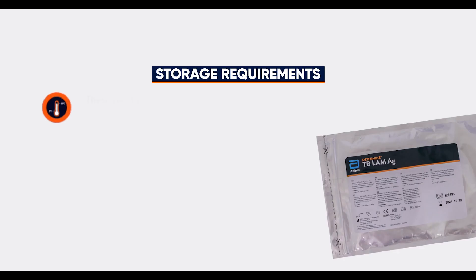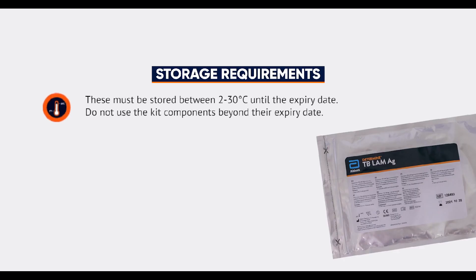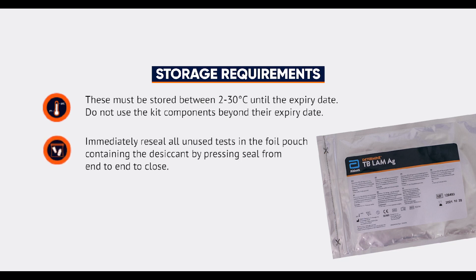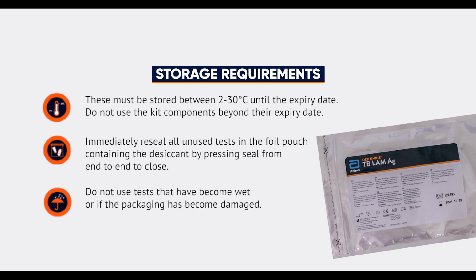The Determine TB-LAM antigen test cards have specific storage requirements to maintain quality and reliability. These must be stored between 2 and 30 degrees Celsius until the expiry date. Do not use the kit components beyond their expiry date. Immediately reseal all unused tests in the foil pouch containing the desiccant by pressing the seal from end to end. Do not use tests that have become wet or if the packaging has become damaged.